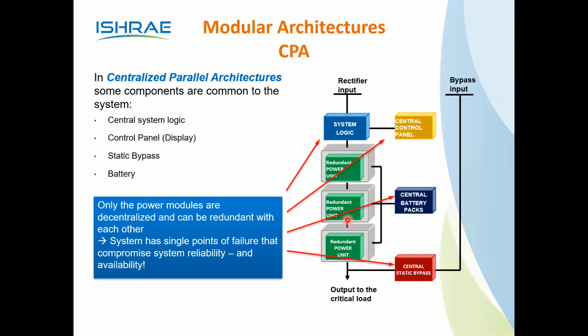What will happen if the system logic fails? That is, if the intelligent module fails, the entire thing will drop. The load will drop. So no redundancy. Again, bypass: if the bypass fails, again no redundancy. If two units fail here, the load automatically goes to the bypass. Again, the bypass is a single component, so there is no redundancy. The control panel is only one control panel. If there is any problem in the control panel, you cannot monitor the status, what is going on inside the UPS system, what type of load it is handling, what percentage of load it's handling. No clue. Again, there are chances for a single point of failure.